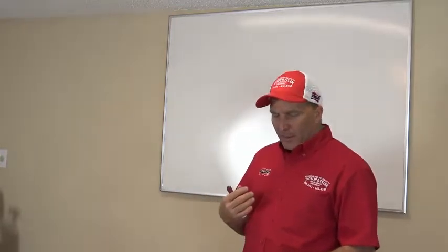Ryan, I went to your condenser, man, and I was checking your pressures and temperatures and your electrical. One of the things that I do is I check the amperage draw of your system. I put my amperage mode on hold, and I put it on max. So when I started your system, I brought my meter here to show you. See how it's drawing 115 amps on there? When your system goes to start, it draws what we call locked rotor amps. And I recorded yours at 115 amps. Now, your run load amps was only 16 amps.